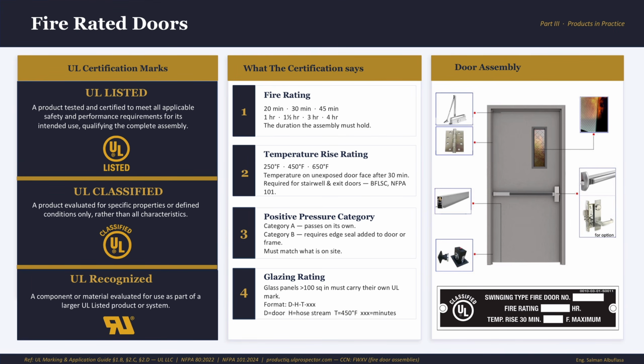So in general, UL listed means the whole assembly system passed, ready to install. UL classified is tested for one specific thing only, and UL recognized is just a part of something bigger, a bigger listed system. That's it. And just like we said, NFPA 80 does not require UL specifically. It requires a third-party certification body. UL is just the most common one you will see.